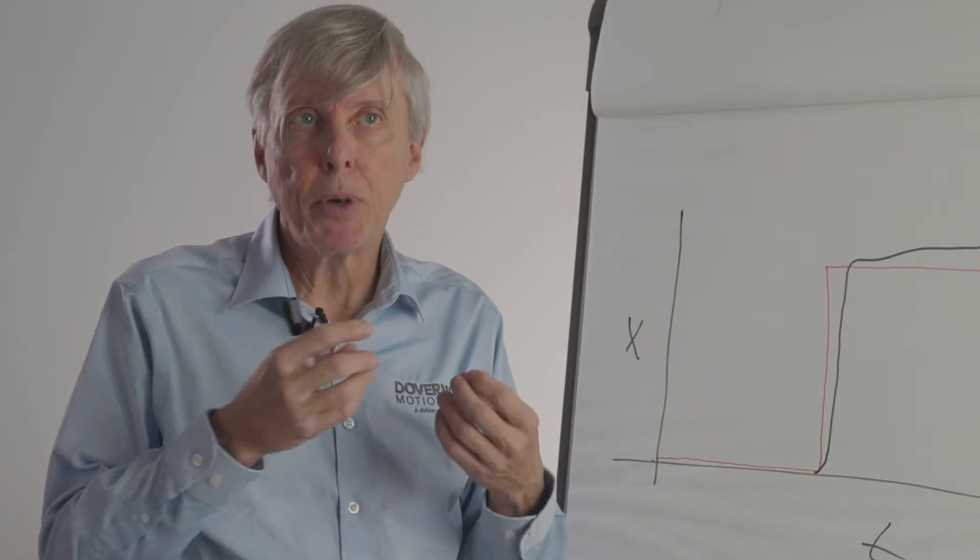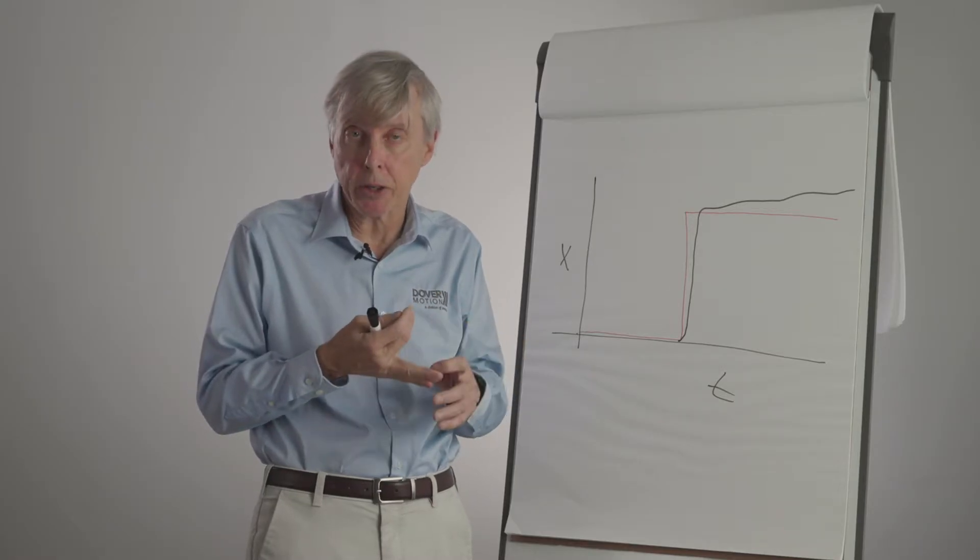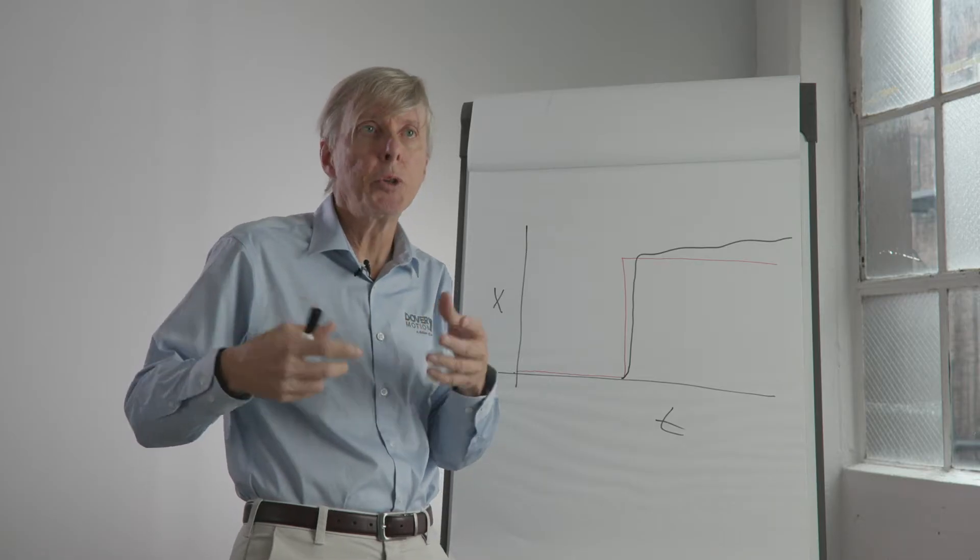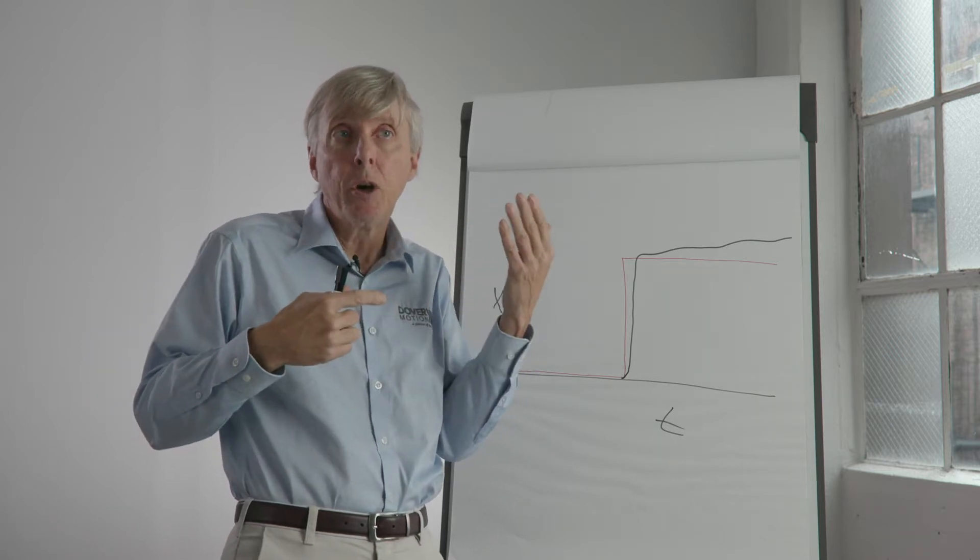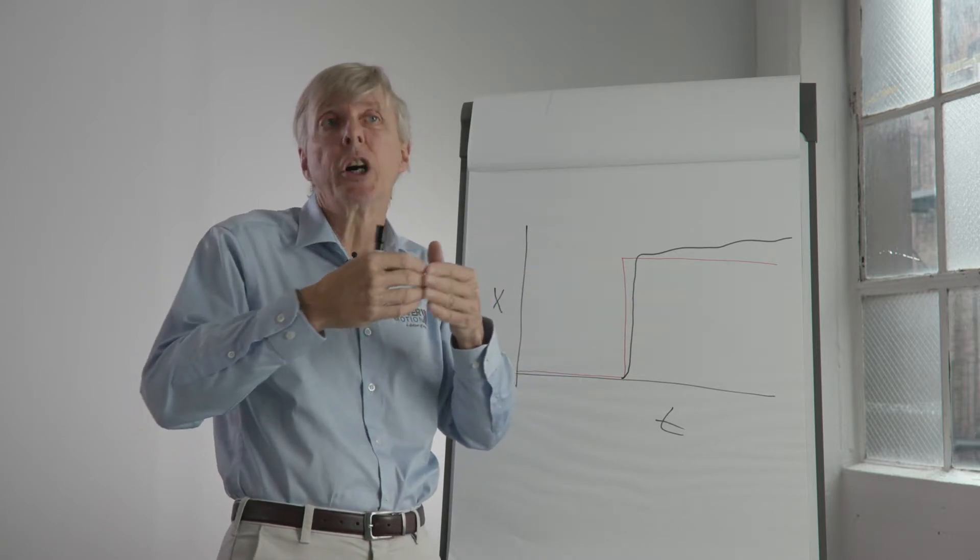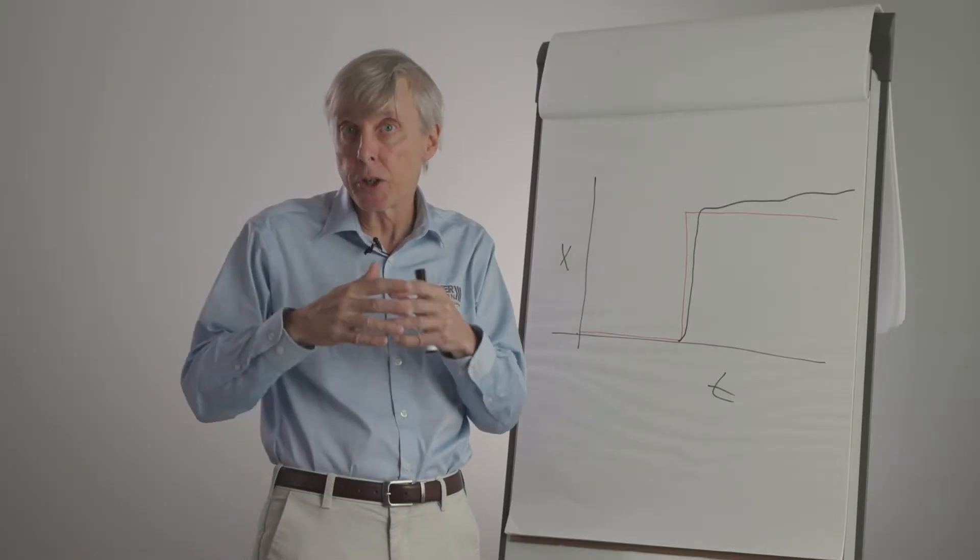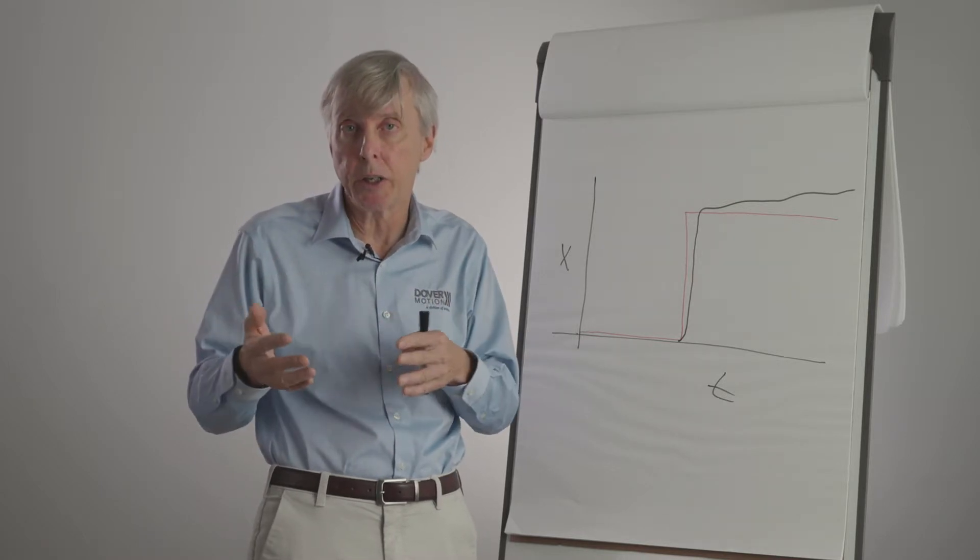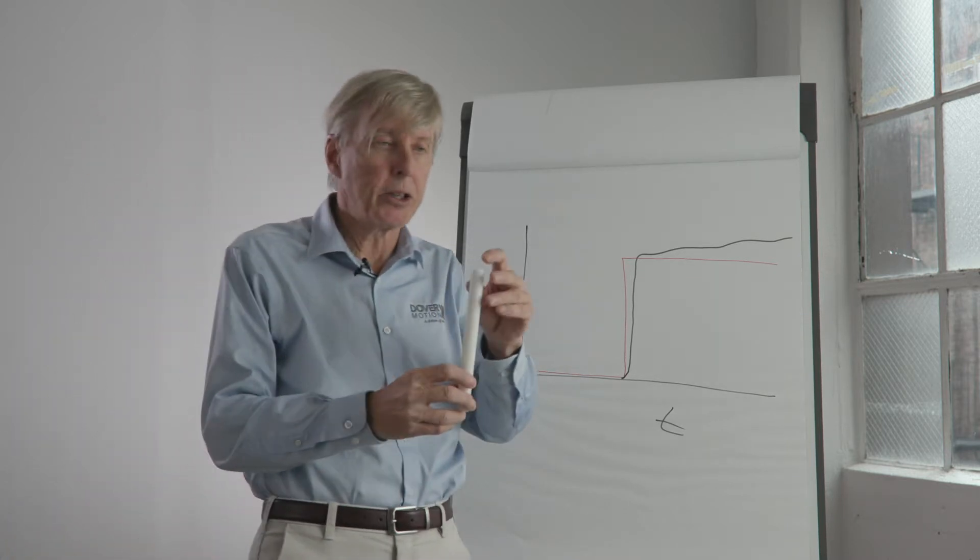The way that this is solved is by turning the open loop product into a closed loop product. In this case, a position feedback device is added, typically either a strain gauge or a capacitance gauge, and a servo controller is used. And one or 2,000 times a second, it measures where is the end of the piezo and where is it supposed to be and is continuously adjusting the voltage to keep it in the right spot. Well, that does certainly improve it, but it also dramatically increases the cost and the complexity of the system. But the dominant problem in the piezo stack is its length.